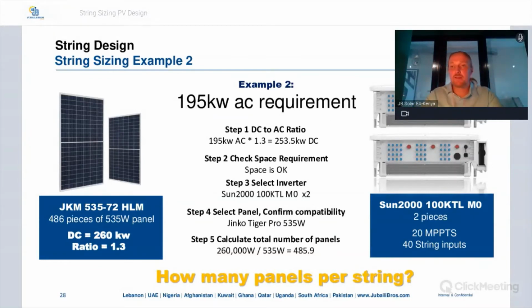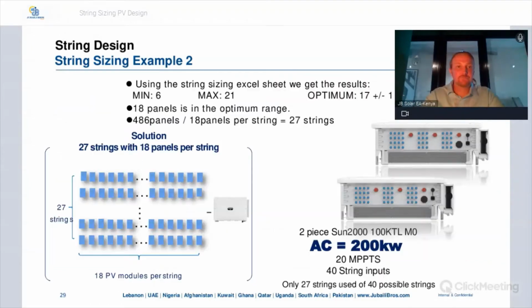Now, how many panels per string? If you use the string sizing tool, you get these results. At the top, the minimum number of panels is 6. The maximum number of panels is 21. And the optimum range is 17 panels plus or minus 1.